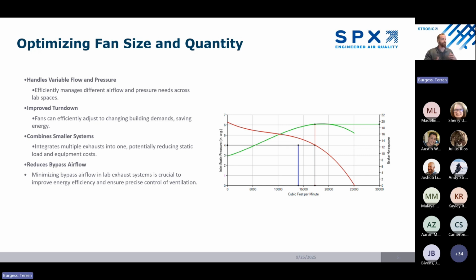It means we're not running fans at max speed when only part of the system is in use, which is going to translate to a major energy savings. Another advantage we have is the ability to combine smaller exhaust streams into a single manifolded system, right? So instead of running multiple independent fans, we can integrate them into one multi-fan array. What this is going to do, not only is it going to lower the static load, but it's going to reduce your equipment cost and create a more consistent plume dispersion.